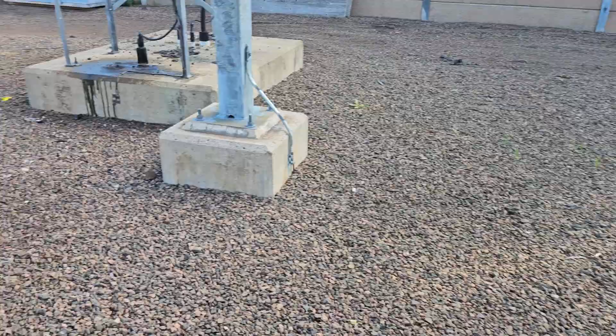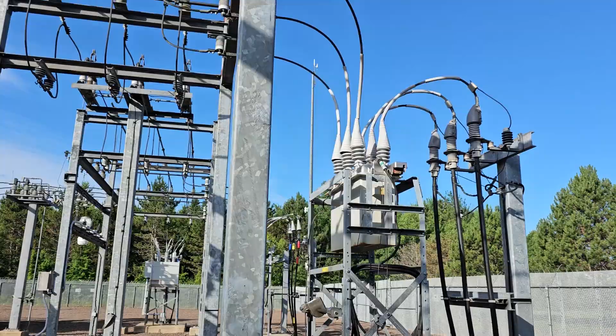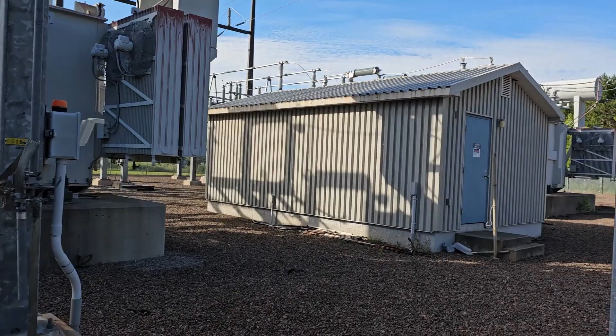So basically what we did, we don't want to close in that circuit switcher and just pick up all the customers off that. So I've got these other 2 reclosers open electronically from inside the sub. So the feed's going into that, but it's open internally. Got that disconnected. We've got this guy disconnected internally, and the one that blew up is isolated. So we're gonna go inside the building, remotely close in that circuit switcher. You can probably capture that on video. And once that's closed, we'll pick up the remaining customers out on the line. There's not a whole lot of load on the line today, so I'll be able to do that remotely.